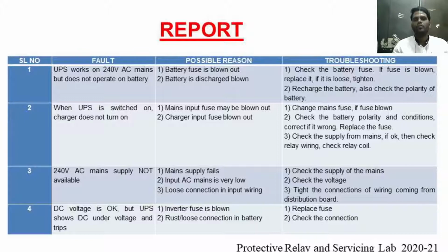So how do we resolve this? What is the troubleshooting method? Check the battery fuse. If the fuse is blown, replace it. If it is loose, tighten it. Or recharge the battery. Also check the polarity of the battery.